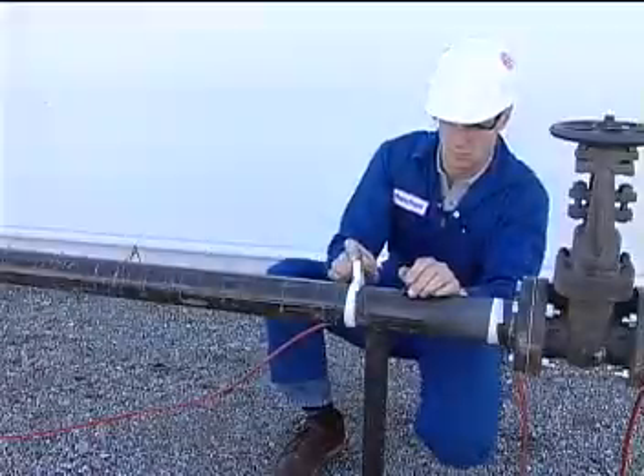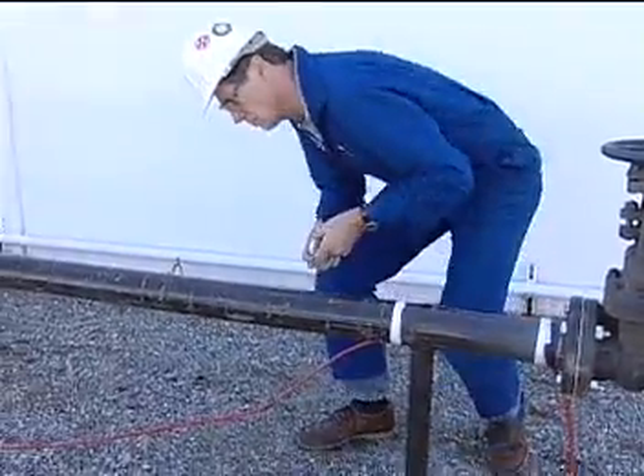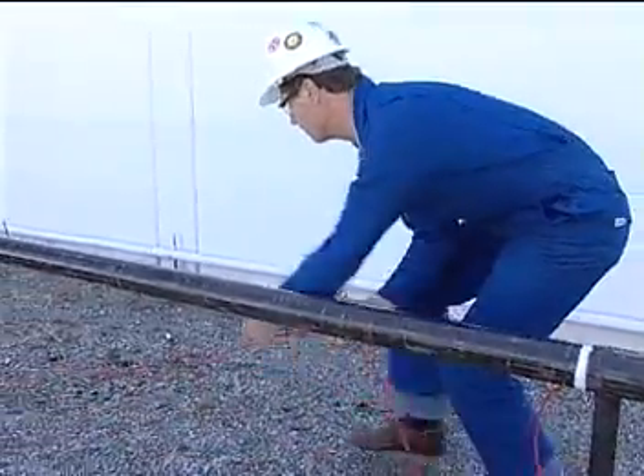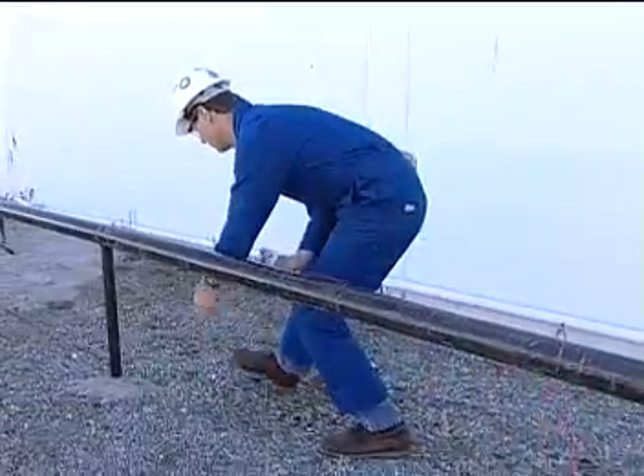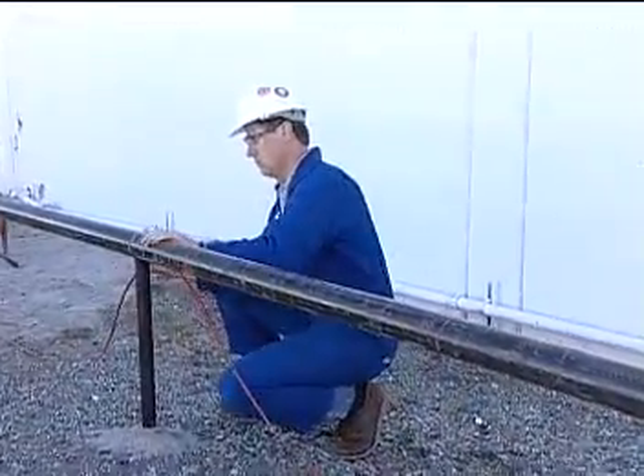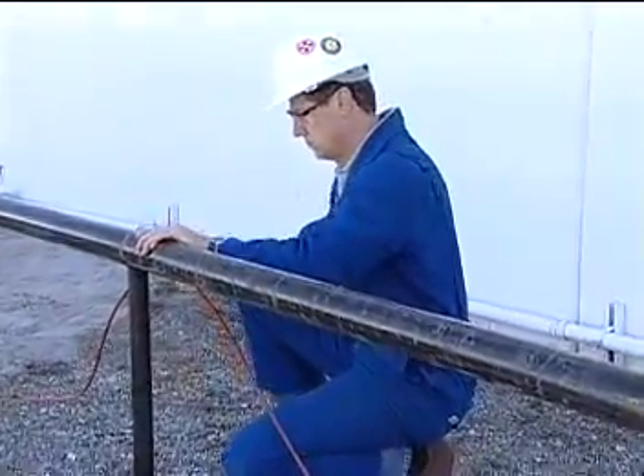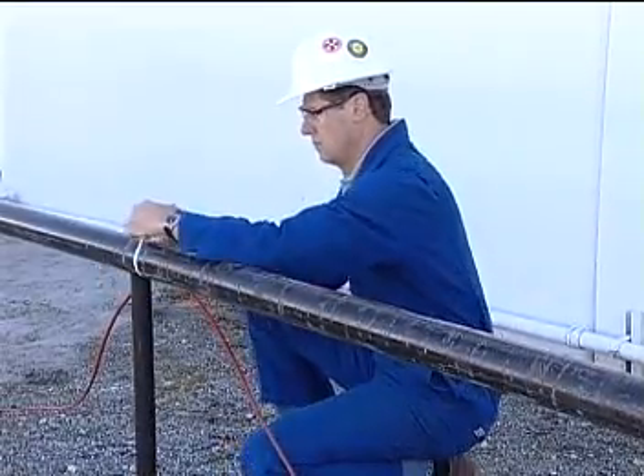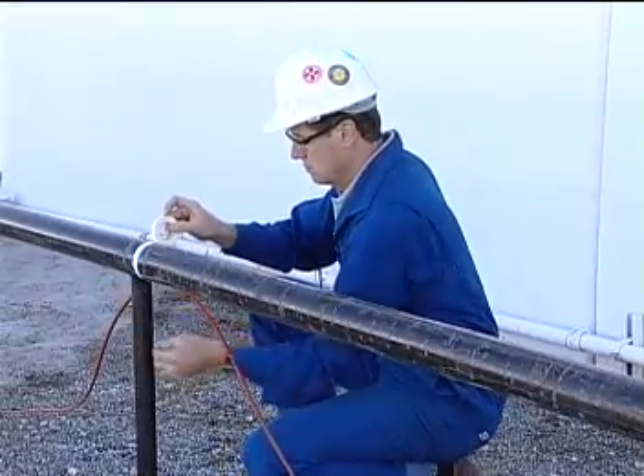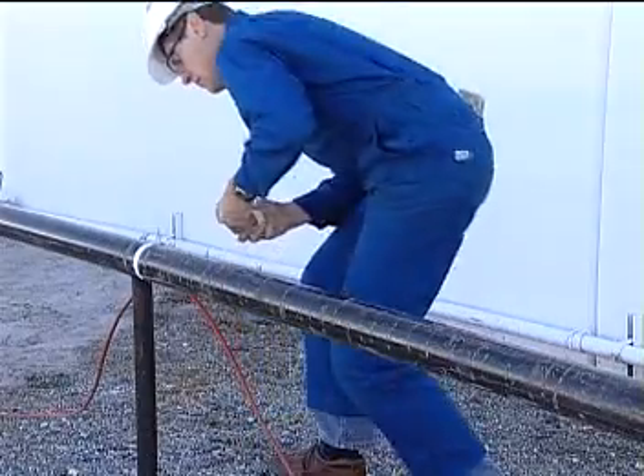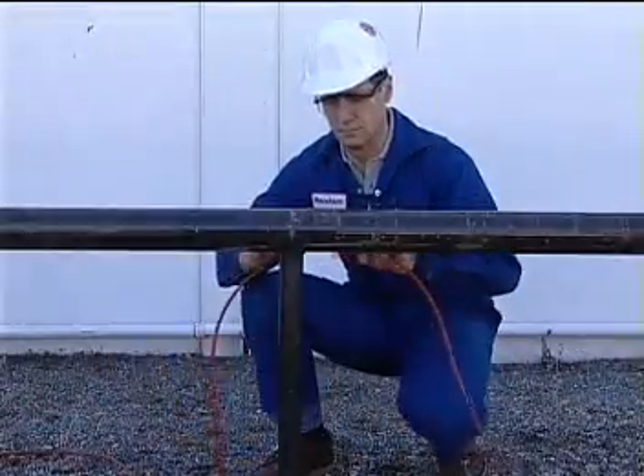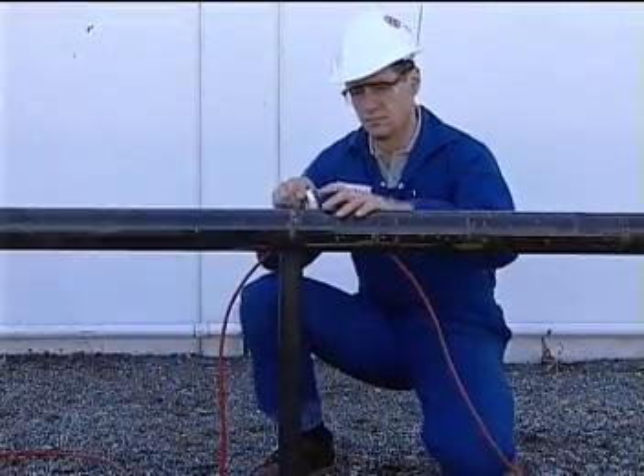If the installation has larger diameter pipes or if the system requires redundant cables, an additional run of heating cable will need to be installed. There are 2 methods of doing this: spiraling the cable or using multiple runs. When the design requires the heating cable to be spiraled, install the cable over the entire run of the pipe, attaching it every 10 feet. Your cable should then be hanging in large loops.